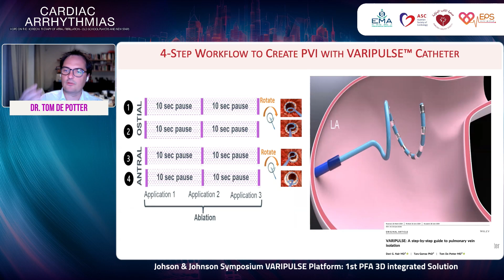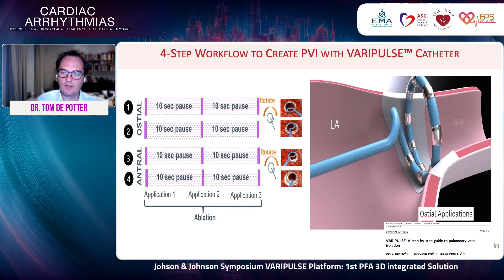atrial tachycardias. The result of this is a very standardized workflow, which you see here in this animation, where we recommend to deliver 3 applications in a single position. This is automatic. Then rotate the catheter and again deliver 3 applications. Why rotate? To maximize overlap and to maximize the probability of PV isolation. The waiting time between applications is for safety reasons, an observation we made in the human studies.